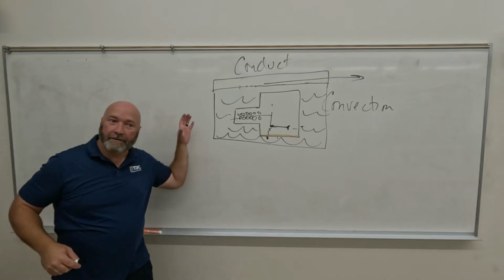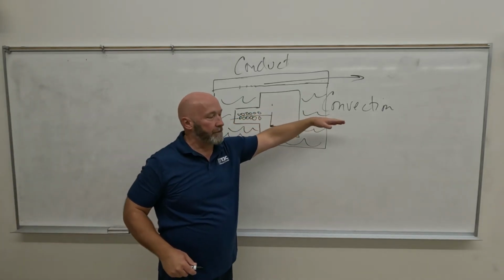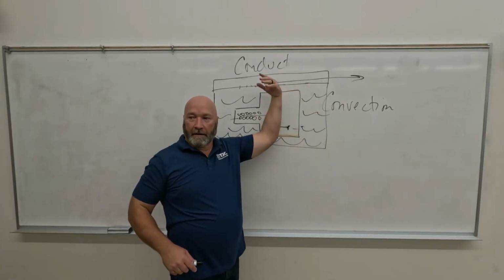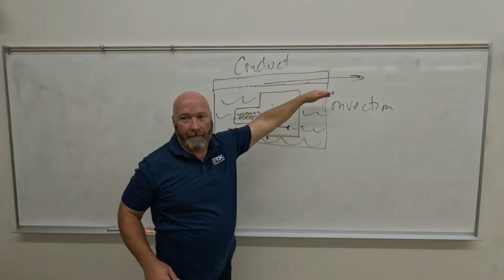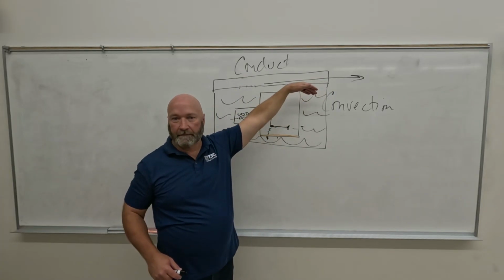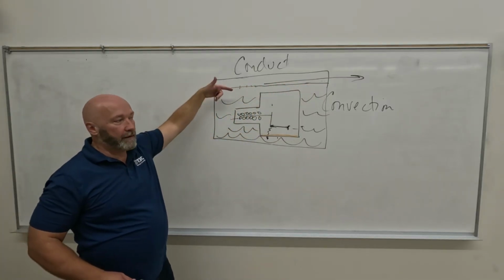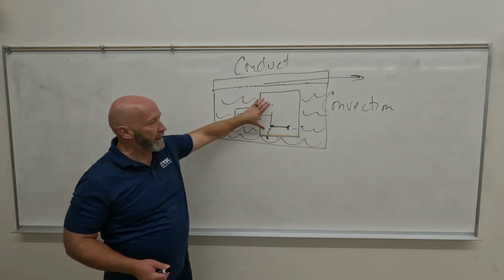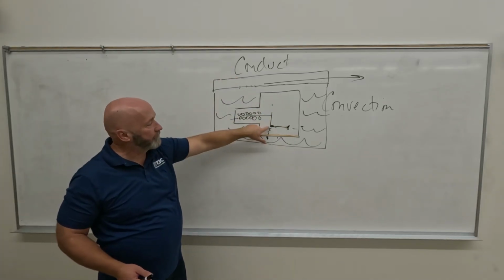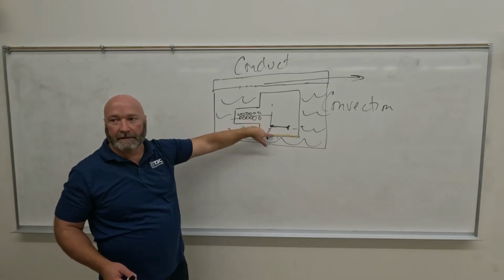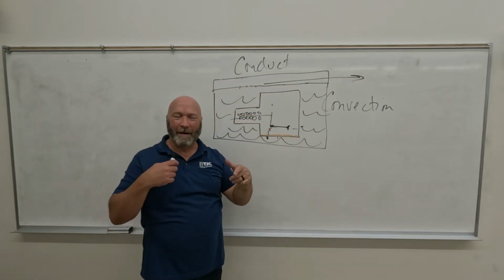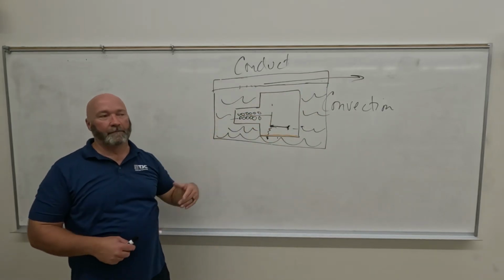Okay, so with it blowing the air out into the room, what do you suppose it's doing? It's taking some of that heat with it. As it cools down, it reinflates, sucks more air back into it, and further cools it down. Okay? So we cool the tube down three different ways. We spread out the heat, and that's with conduction, right? We thermally radiate from the anode to the glass, and then, as best we can, we convect it out into the room. Again, that might be an active fan, or it may be more of a bellows type fan.